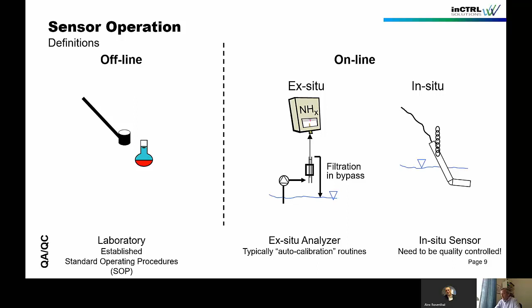So you have a lot of self-diagnosis, but I still recommend to do and set up that external quality control. Okay, so a couple more definitions. I like to split the different phases of the life cycle of a probe, and I start with commissioning. What we include in commissioning is installation and something we call base calibration or initial calibration.